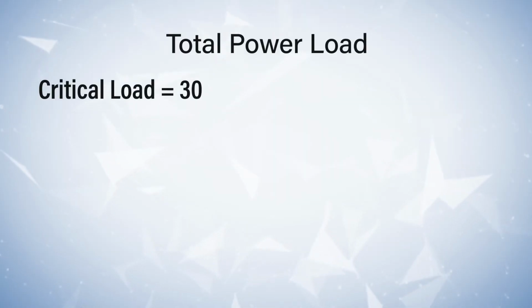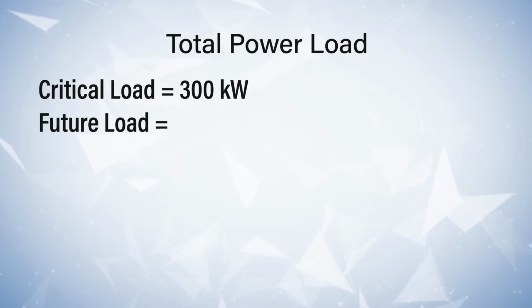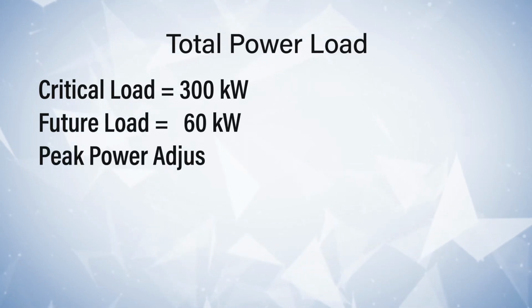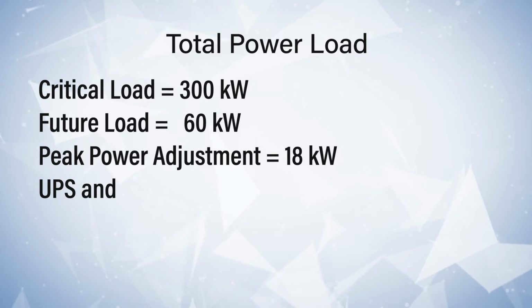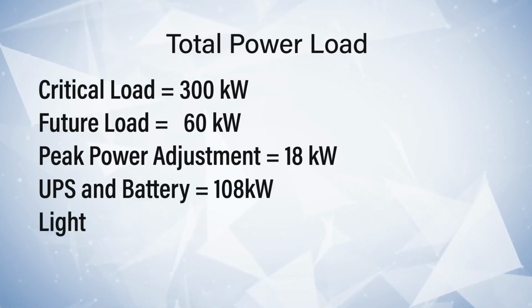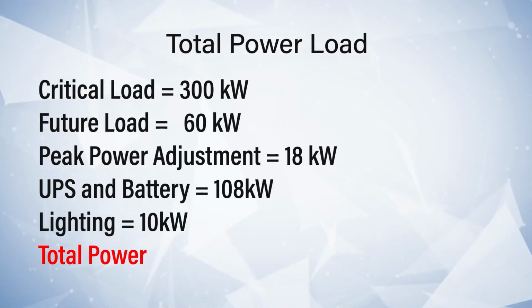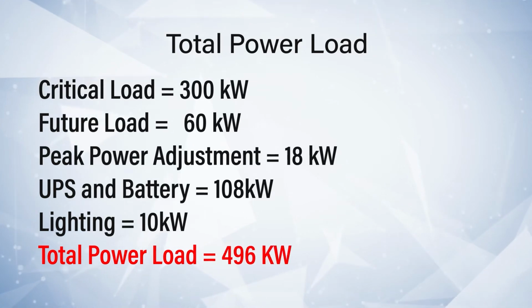Now moving on quickly, let's calculate the lighting load. Estimating it will be 2 watts per square feet. So for example, if we have 5000 square feet, it will be 10 kilowatts lighting load. Now let's add up all that for the total power load. So our critical load is 300 kilowatts, future load is 60 kilowatts, peak power adjustment is 18 kilowatts, UPS and battery is 108 kilowatts, lighting load is 10 kilowatts, total power load is 496 kilowatts.